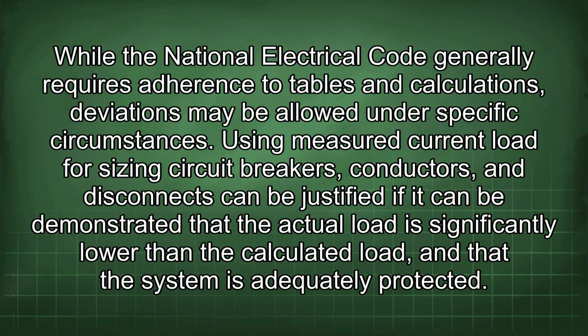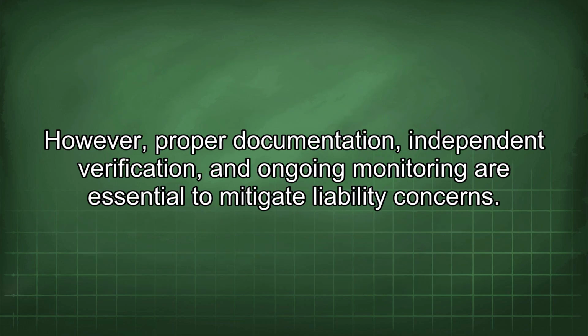While the National Electrical Code generally requires adherence to tables and calculations, deviations may be allowed under specific circumstances. Using measured current load for sizing circuit breakers, conductors, and disconnects can be justified if it can be demonstrated that the actual load is significantly lower than the calculated load and that the system is adequately protected. However, proper documentation, independent verification, and ongoing monitoring are essential to mitigate liability concerns.